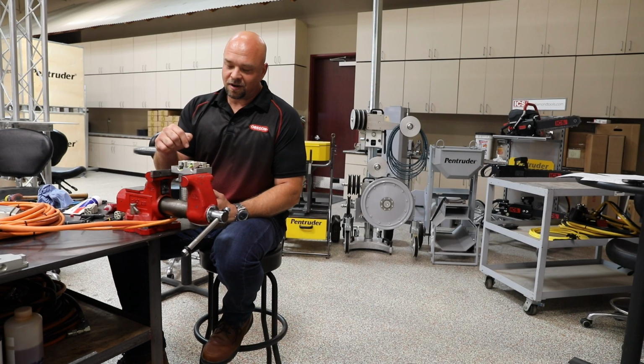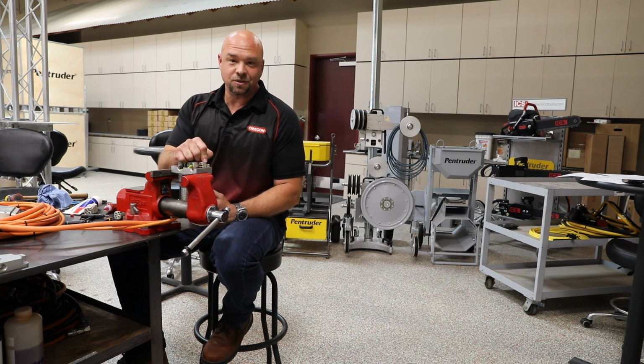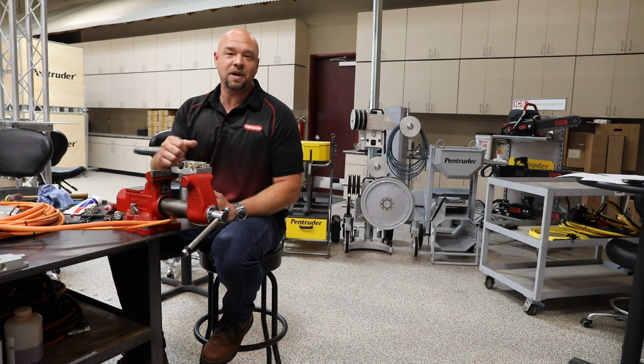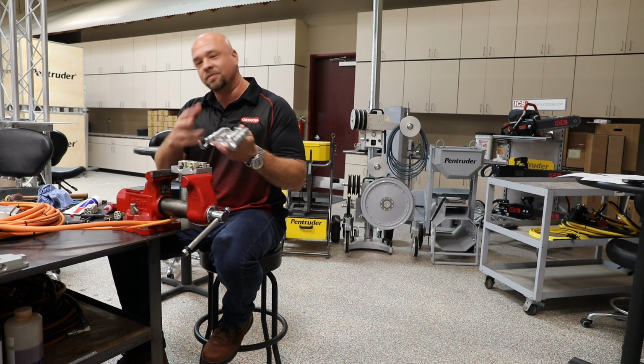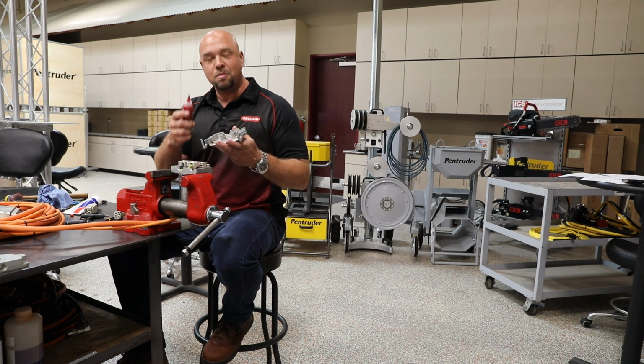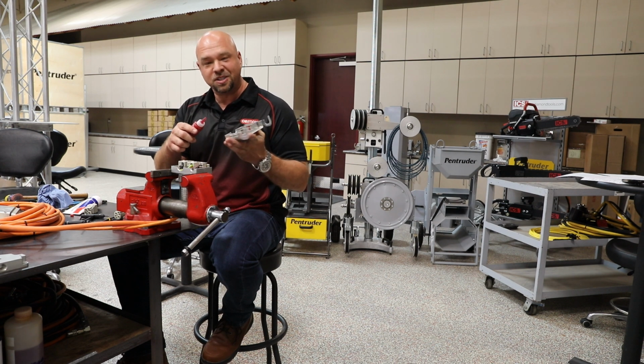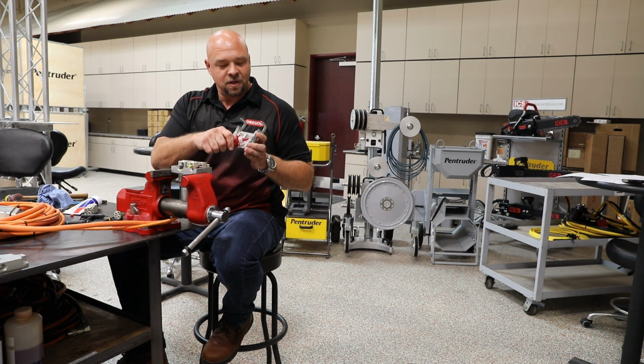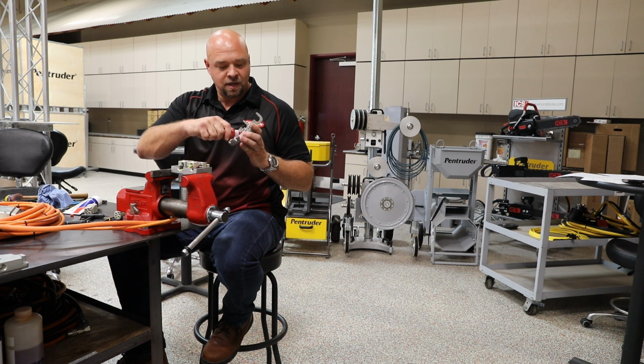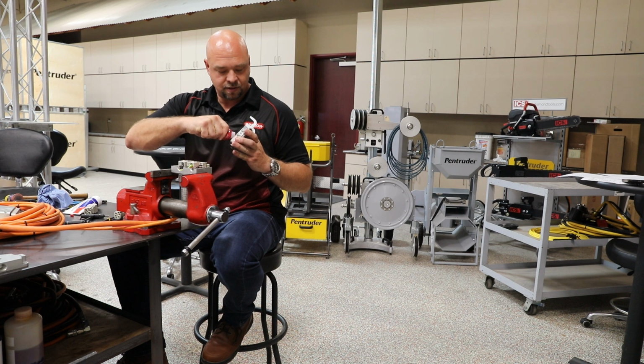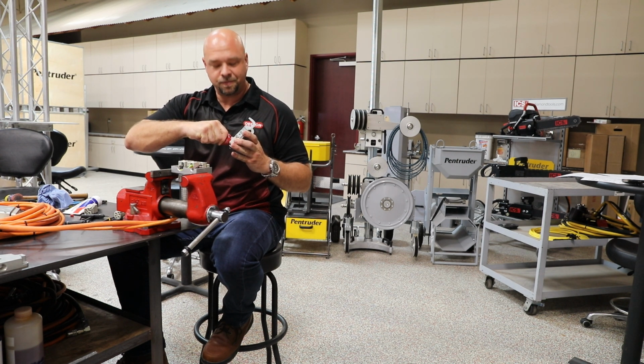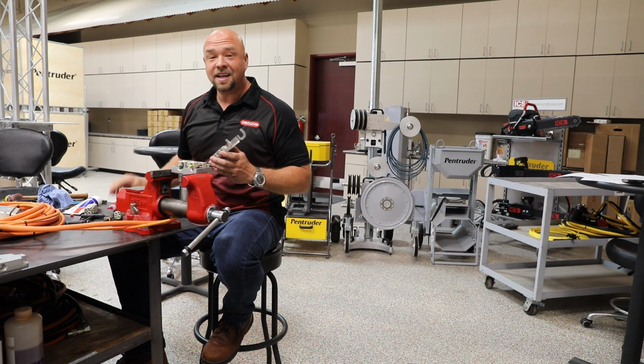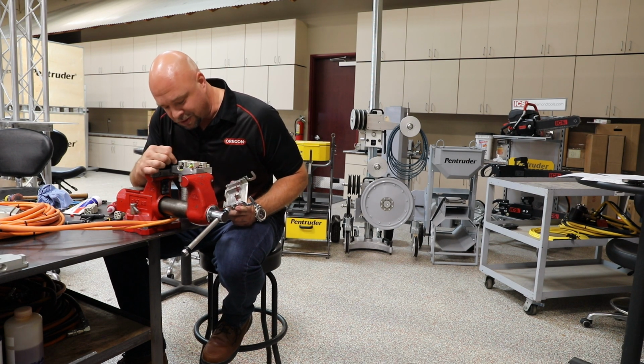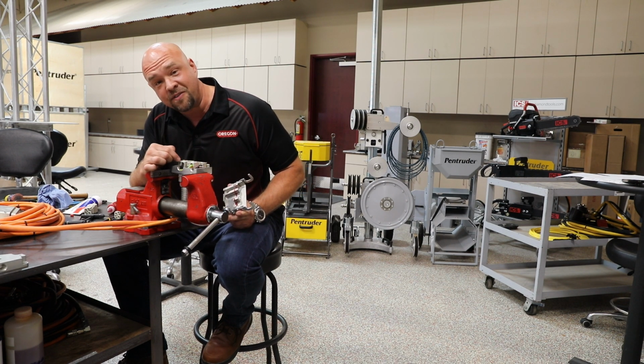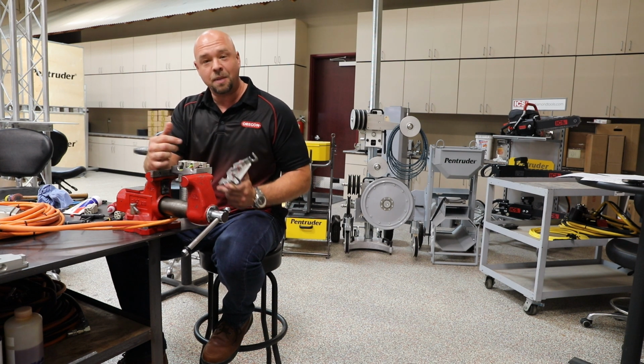Alright, so we've talked about our high voltage connectors and our low voltage connectors, and it's time to close everything back up. It doesn't matter if we're talking about a cable end or a motor. Again, using some Loctite 518 and making sure that waterproof gasket is created is important. So before we put it back together, I'm going to apply some 518 around the keyway areas of the housing. I'm going to give one last visual inspection before I close this back up, to make sure no wires are hanging out, that I've filled all the holes with dielectric grease, and kept everything as tight as I can.